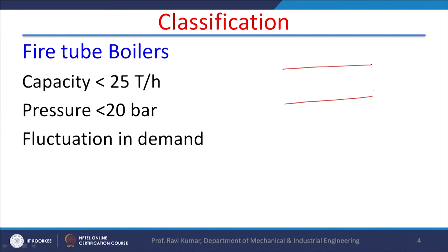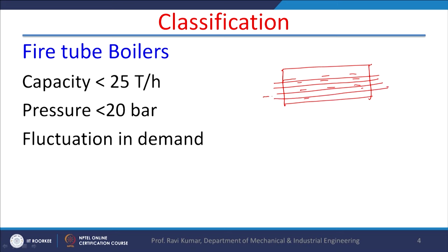Regarding the classification of boilers, broadly they are classified into fire tube boilers and water tube boilers. In a fire tube boiler, there is a shell filled with water. Through this shell there are one or more tubes, and in these tubes the flue gases are flowing. Flue gases are gases generated after burning the fuel and are at a very high temperature. When these flue gases pass through the shell, heat exchange takes place between the gases and the water, and steam is generated. These are known as fire tube boilers because there is fire inside the tube.